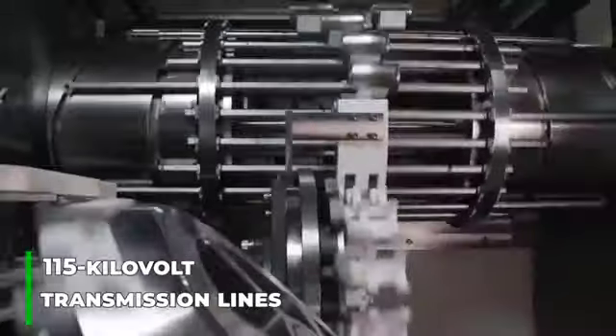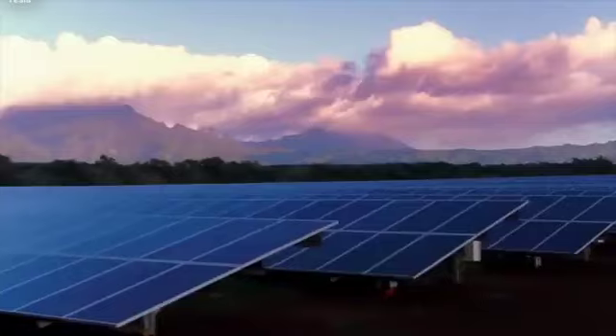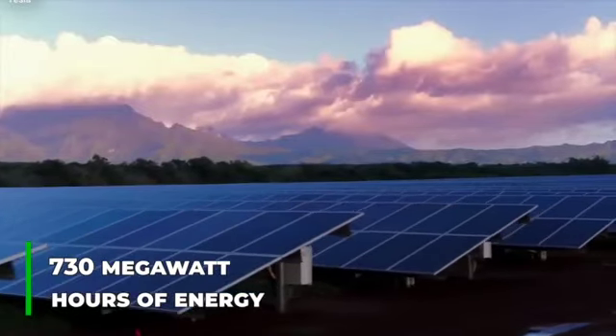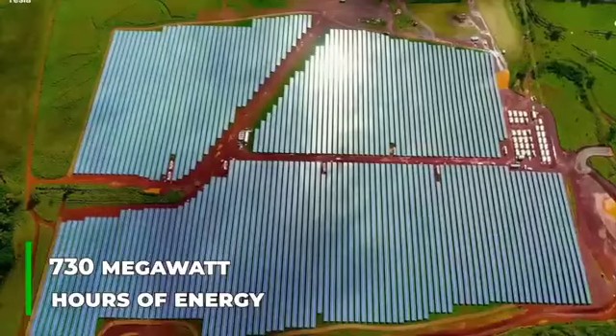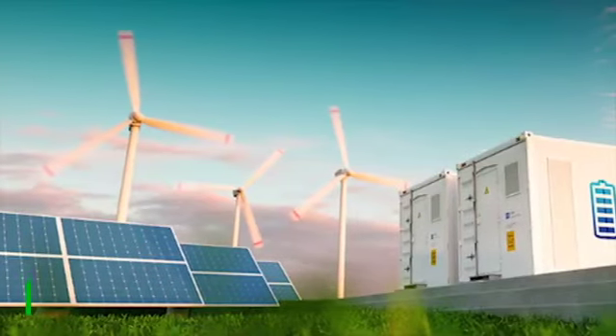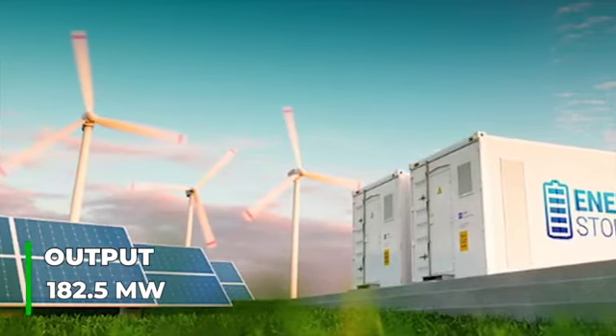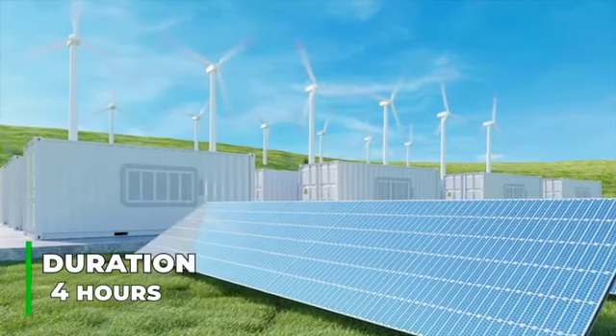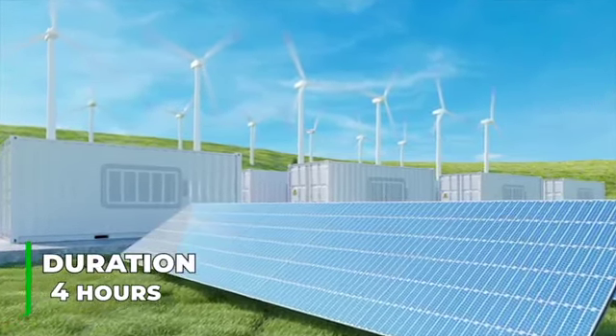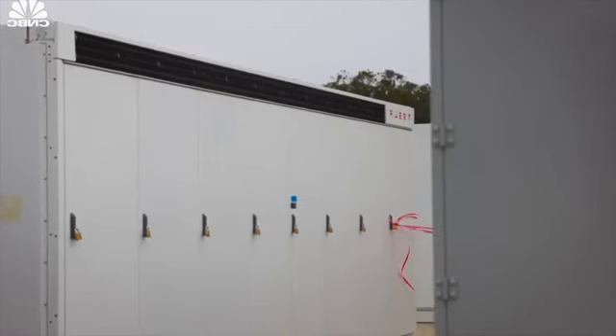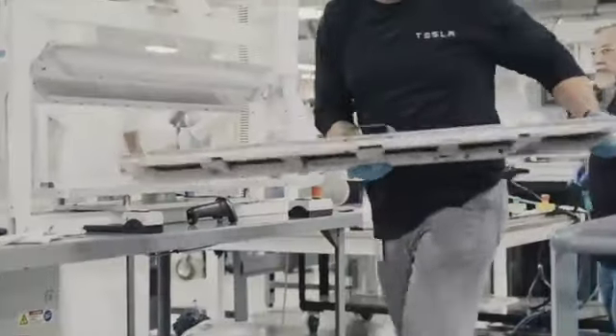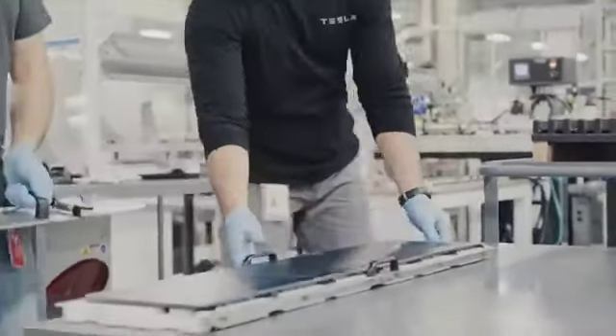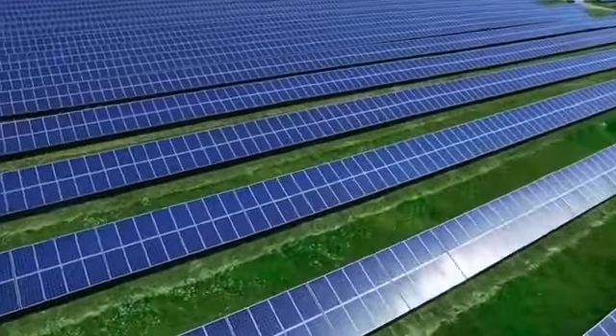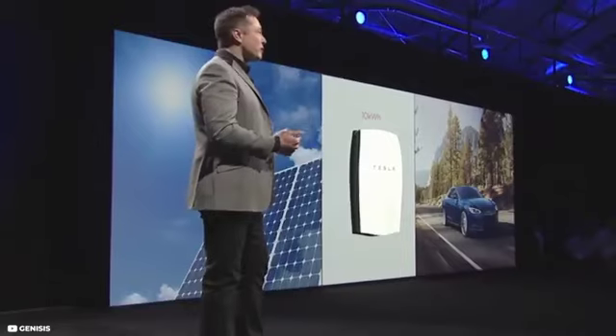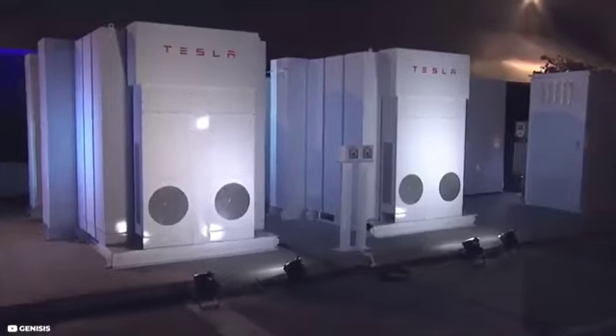With a robust capacity, the BESS can both store and release up to 730 megawatt hours of energy into the power grid, capable of reaching a maximum output of 182.5 megawatts for durations of up to 4 hours during peak demand periods. The strategic adoption of battery energy storage stands as a pivotal factor in the integration of renewable energy sources, particularly solar power. Simultaneously, this approach substantially elevates the overall reliability of California's ever-evolving energy supply landscape.